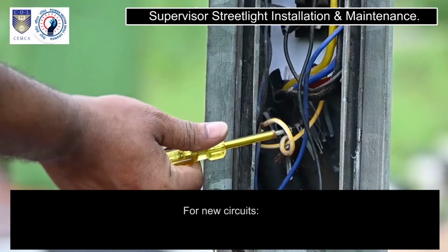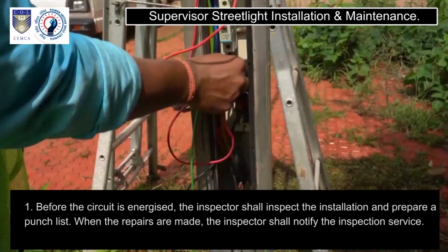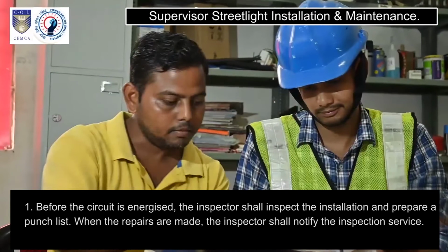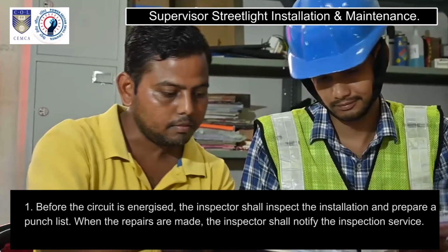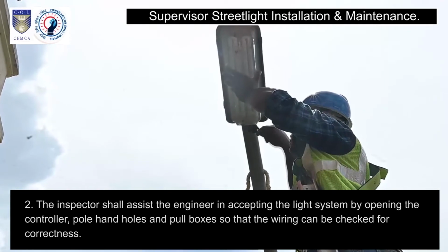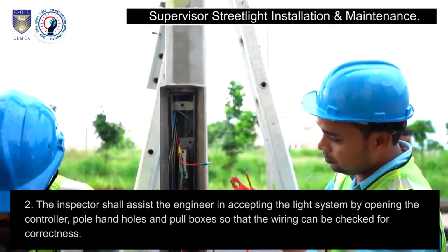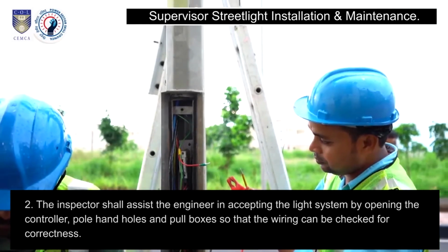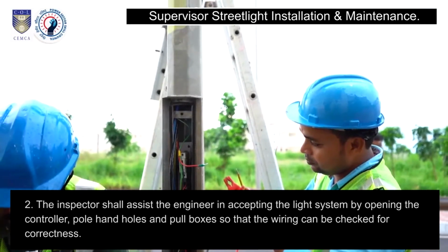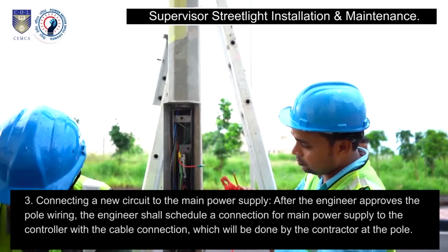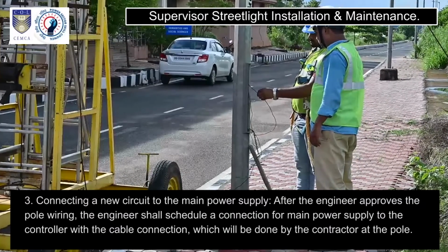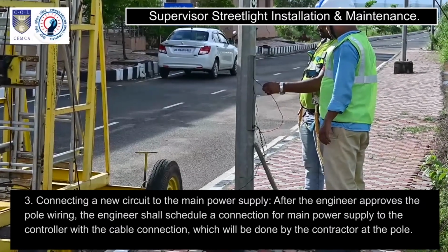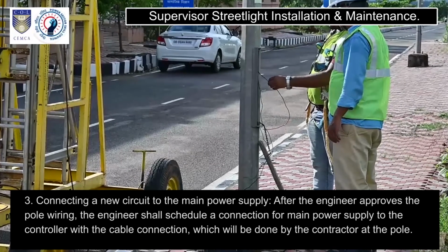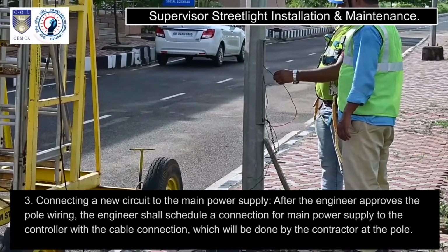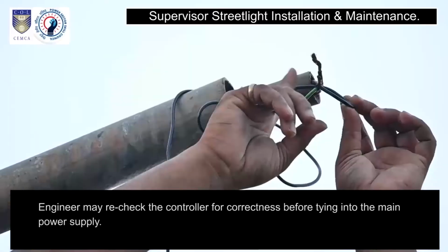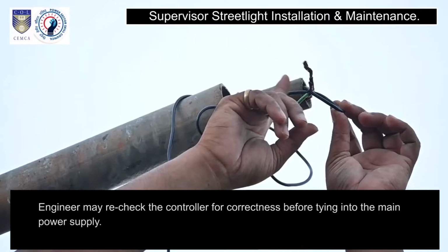For new circuits: 1. Before the circuit is energized, the inspector shall inspect the installation and prepare a punch list. When the repairs are made, the inspector shall notify the inspection service. 2. The inspector shall assist the engineer in accepting the light system by opening the controller, pole hand holes and pull boxes so that the wiring can be checked for correctness. 3. Connecting a new circuit to the main power supply. After the engineer approves the pole wiring, the engineer shall schedule a connection for the main power supply to the controller with the cable connection, which will be done by the contractor at the pole. The engineer may recheck the controller for correctness before tying into the main power supply.